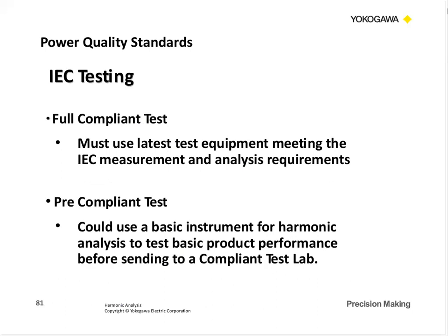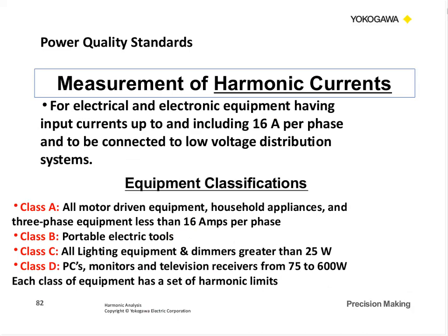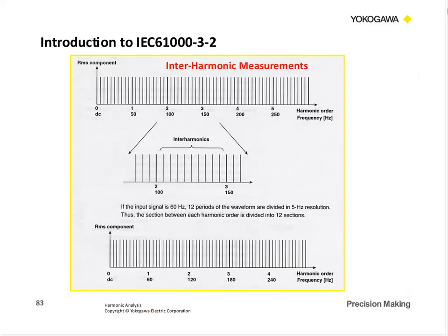And so with IEC testing, you can do a full compliance test, and here you have to use the latest equipment, software, and everything to do that requirement. Now you can do what they call a pre-compliant test, where you could use a basic instrument for the harmonic analysis and get a good idea of your product design before you send it off to a full compliant test lab. So in the IEC 61000, they break it up into different classes of products, and each product has a different harmonic analysis pass-fail.